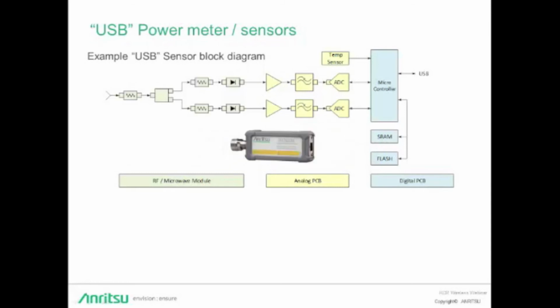In USB sensors, the channel analog signal acquisition hardware, the preamps and the LPF, is integrated along with the RF front end of the power sensor into one small package. So you're reducing the connection of a 1.5 meter long cable to a few millimeters, and thus eliminating the need for calibration of this analog hardware. Along with the necessary frequency and temperature corrections which take place within the sensor, the USB sensor will transfer calibrated and corrected data in digital format to the host PC or handheld.